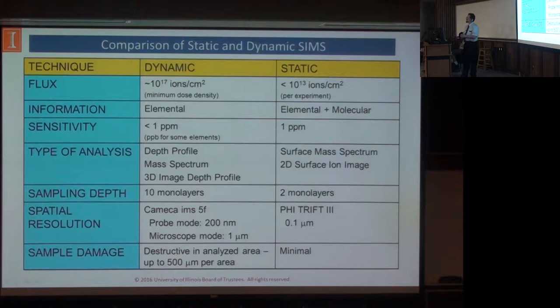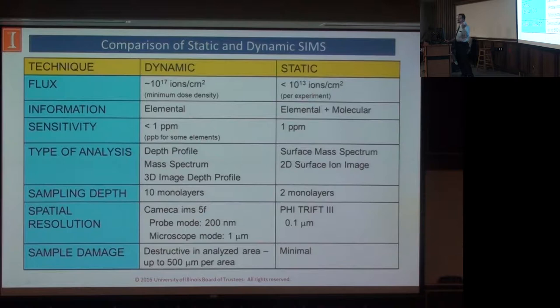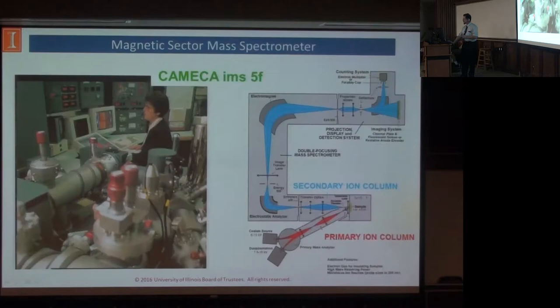Static SIMS came about later and is really neat. The concept is: if we only affect 1% of the surface, is it really destructive? 99% of it's still okay. So if silicon has 10^15 atoms per square centimeter on the surface and we affect less than 10^13 in the experiment, we'll say it's effectively the same — you can come back to the same area and get the same result. When that happens, it allows us to see some molecular things and get 2D surface images. Of the instrumentation we have, one does a very good job for dynamic work and one does a good job for both dynamic and static work.